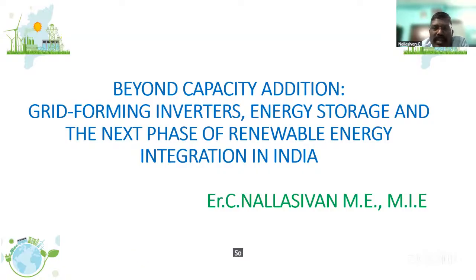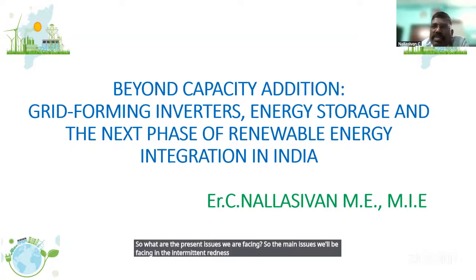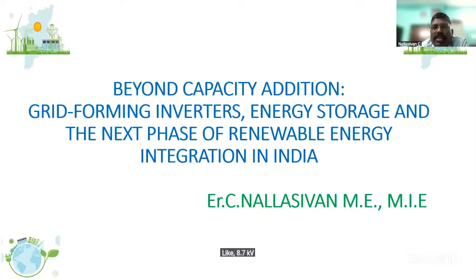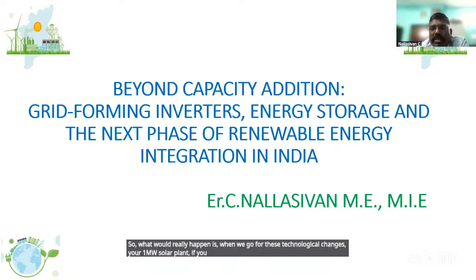So what are the present issues we are facing? The main issue we'll be facing in the intermittent grid is voltage fluctuation. If you take a real case, my 11 kV grid would have a low voltage as low as 8.7 kV. So when we go for these technological changes, your 1 megawatt solar plant, on a per unit basis, by changing this firmware concept, there will be a reduced active power.